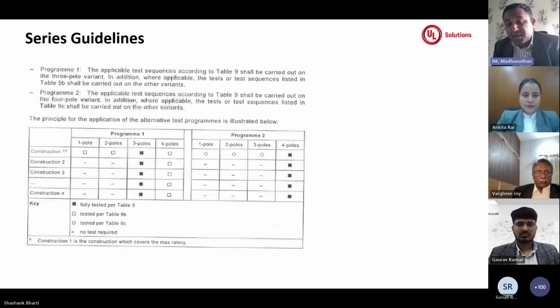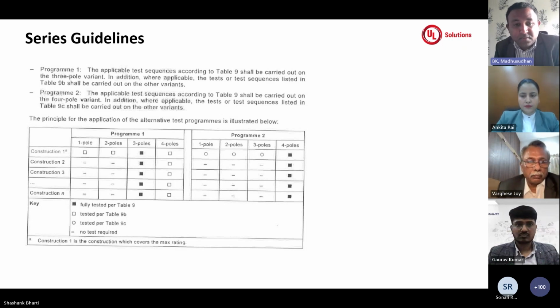The standard also gives clear guidelines on how to select the samples, and what the base construction and the poles to be selected are. From table 9 and 9A references, we have programs that can be selected based on the manufacturer's declarations, either program 1 or program 2. Program 1 speaks about selecting the samples from the bigger range of breakers, especially the 3-pole range. For example, if the manufacturer is declaring a range from pole 1 to pole 4 and wants to pick 3 poles as the reference for testing, the standard lets program 1 be selected, where 3-pole testing is done based on the requirement, and additional tests for the single pole, 2-pole, and 4-pole are carried out.